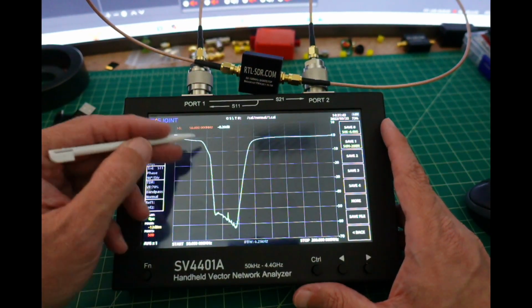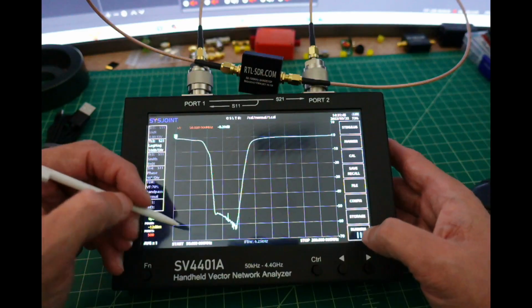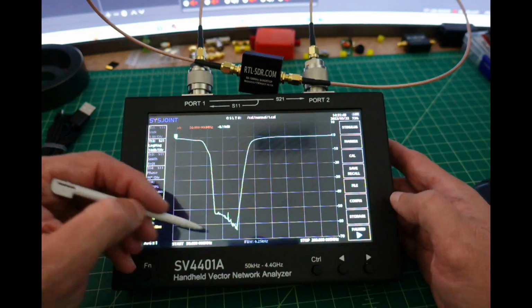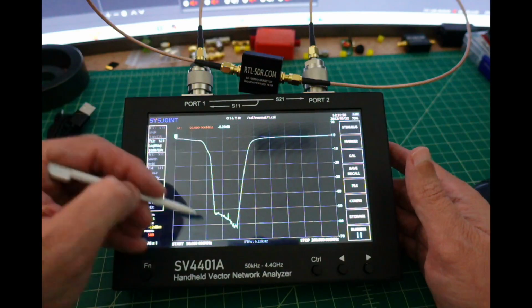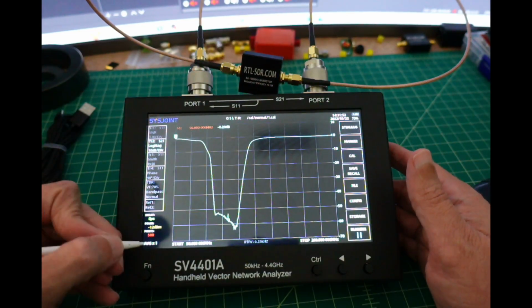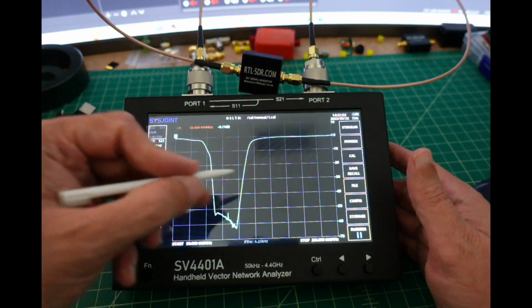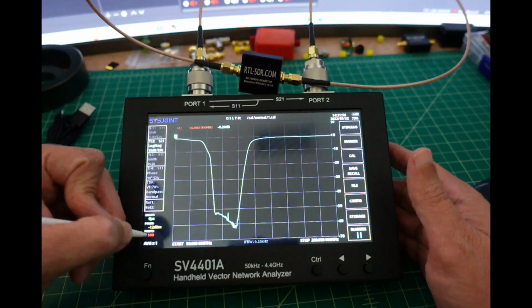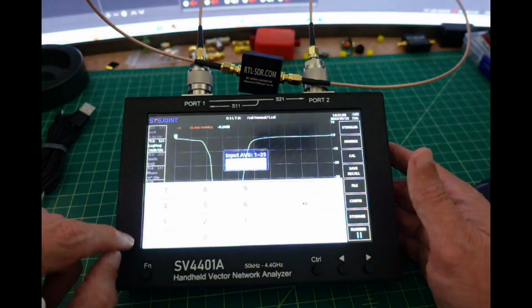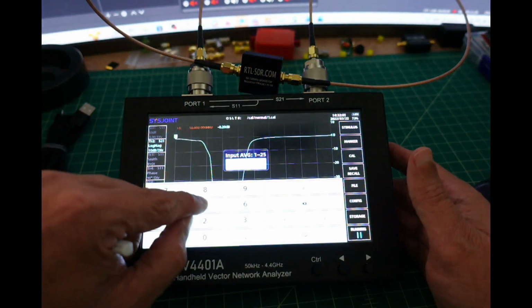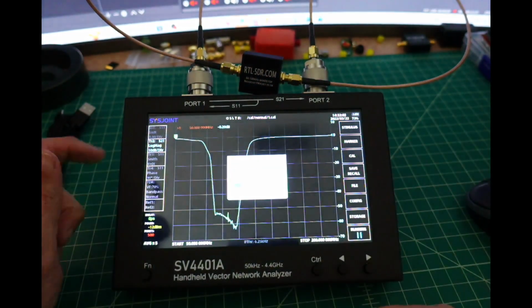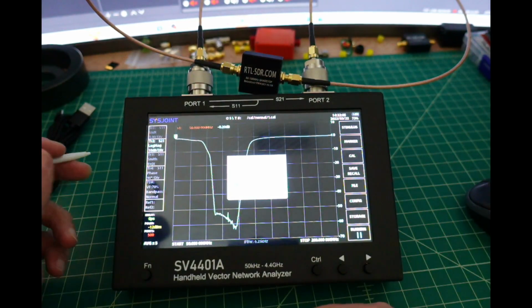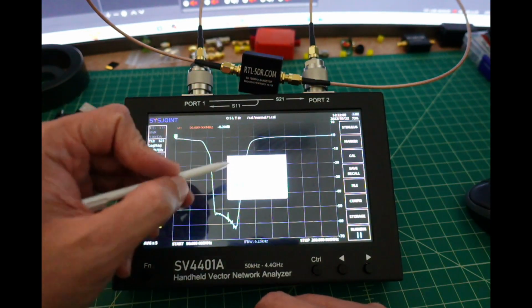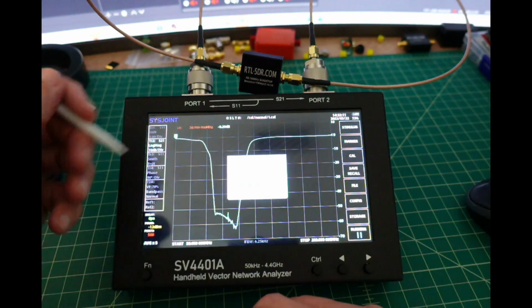Now here the sweep is just running continuously. See this pause button? I can hit pause and it'll stop. Now I'll start it back up, and it's just sweeping. And down here it says averaging 1. So it's just sweeping, showing us, sweeping, showing us. Let me go into averaging. You have to use your finger. And let's say we want to average 5 sweeps before it updates the display. That's a good idea to do averaging, because it gives you a more precise, well, not a more precise, but a more accurate representation of what exactly is happening.